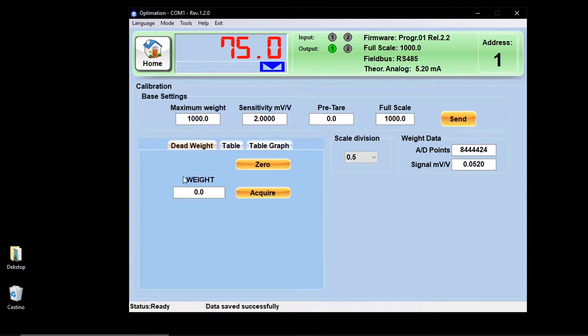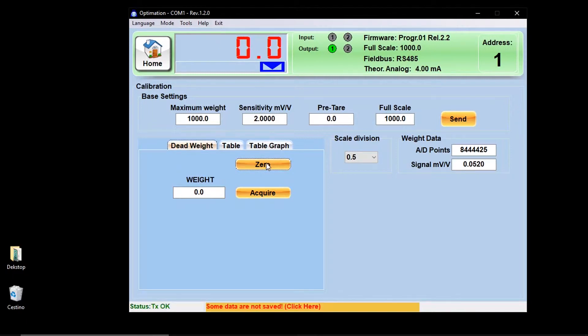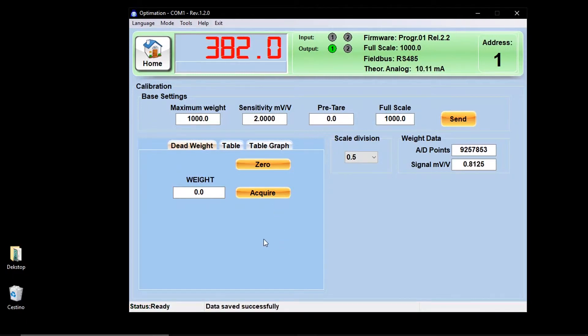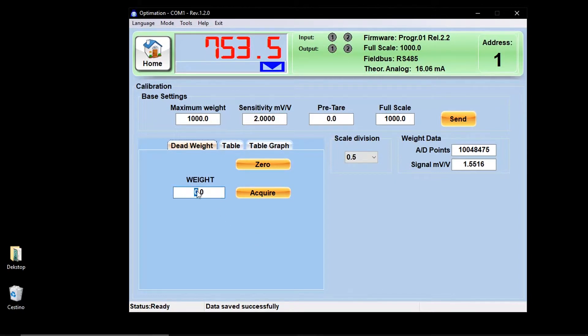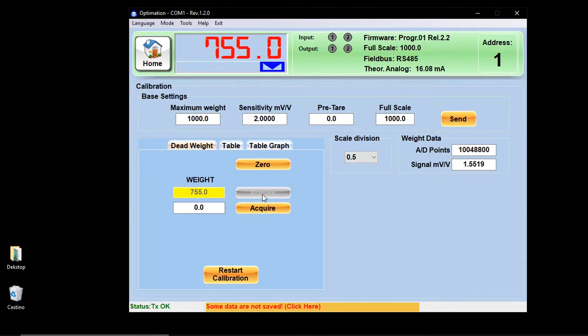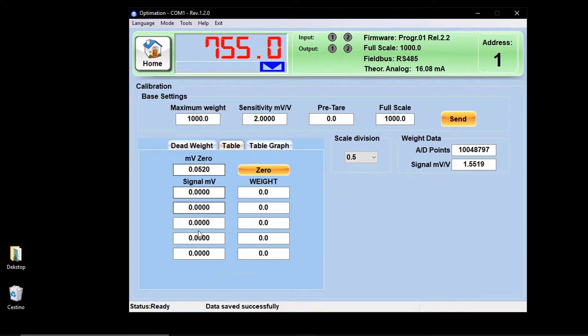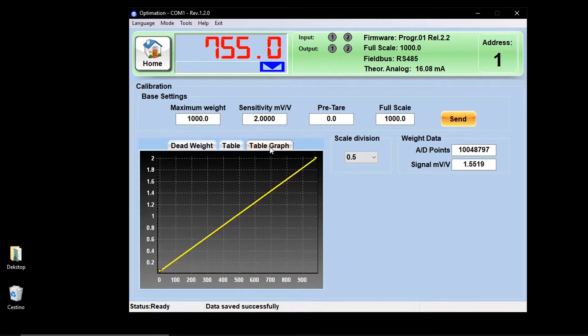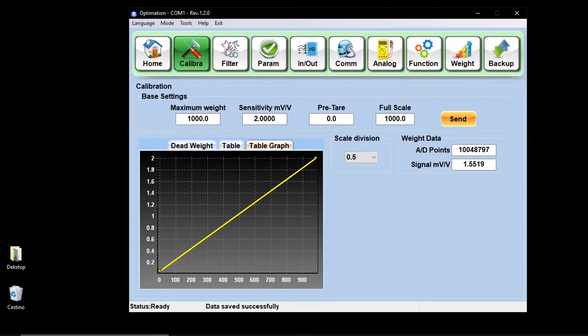It is also possible to calibrate using simple and fast steps. Once the system is unloaded and stable, the zero key can be used to zero the weight. Next, apply a known weight and write in the box its value. Click on the acquire button to perform the calibration with the sample weight. It is also possible to perform table calibration and display a graph to monitor the linearity of the system.